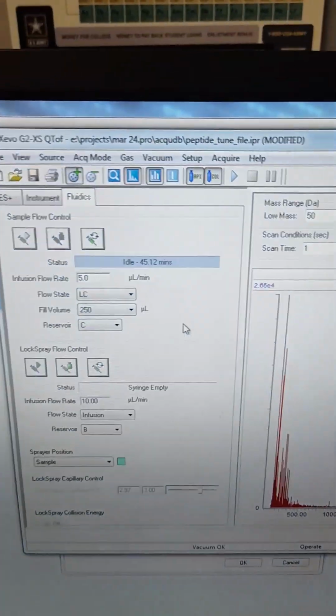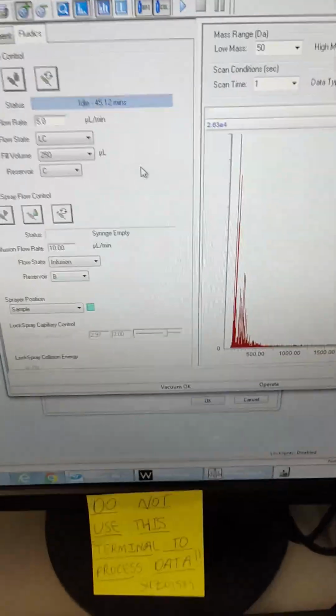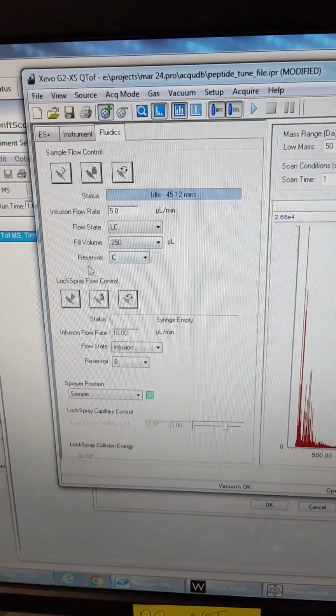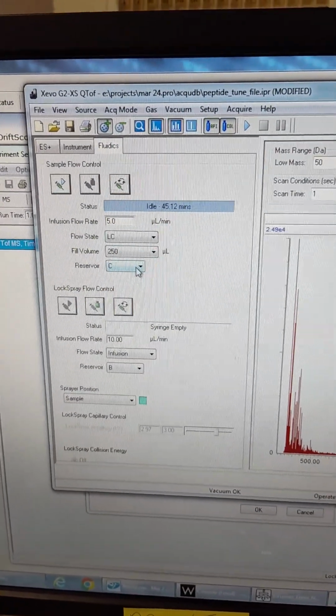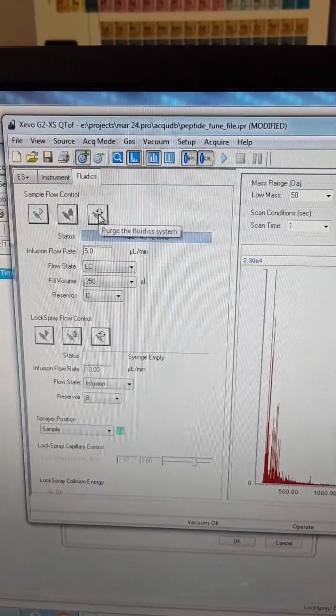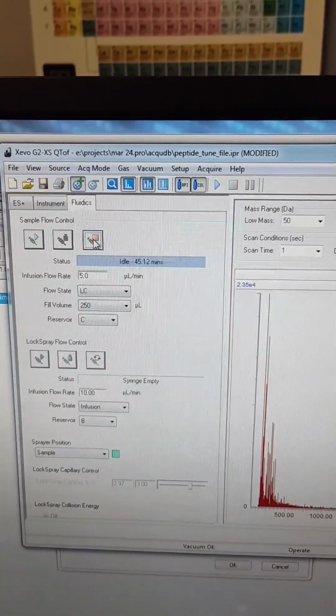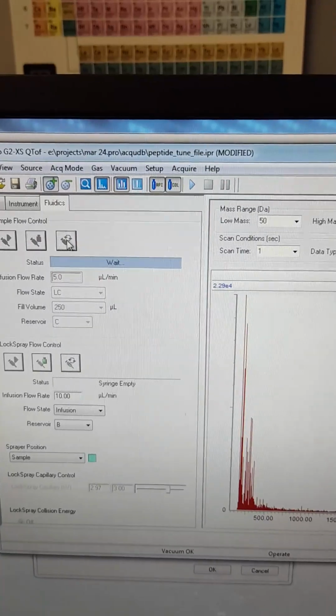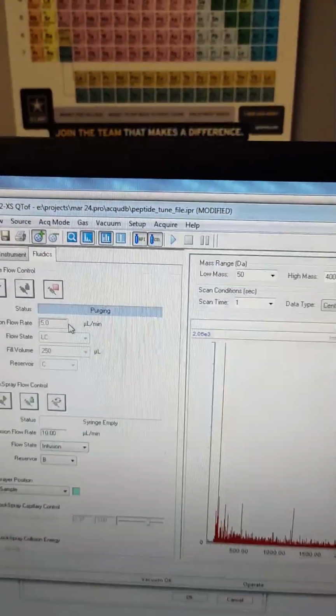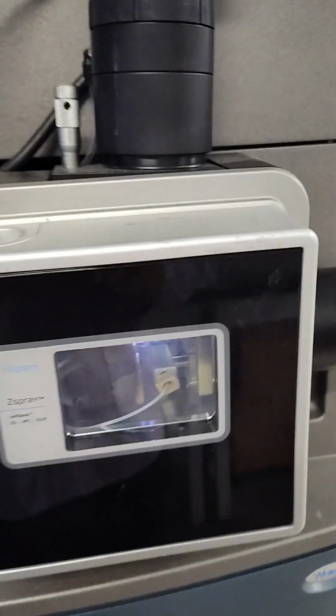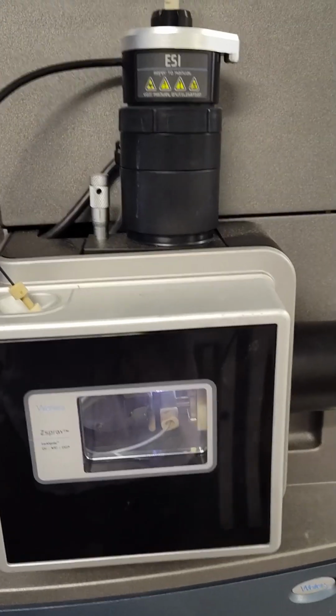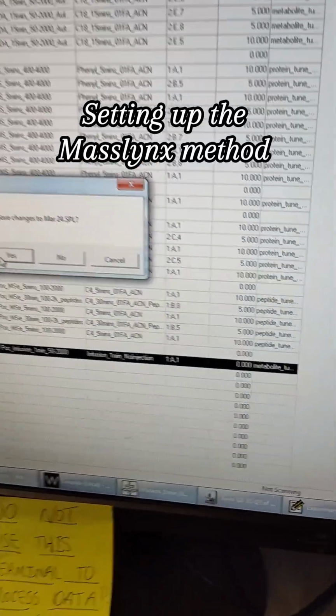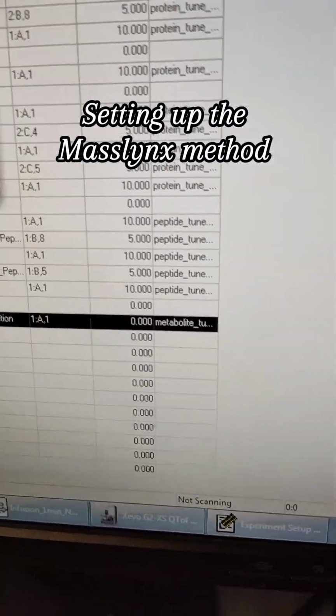And then we'll purge. We're going to go ahead and purge 3 times. Make sure that you are on reservoir C when you hit purge. And then you're just going to hit the purge the fluidic system here on C. We're trying to pump through the actual sample syringe. It's important to do the calibration through the same sample syringe that you're spraying your sample through so you get the best calibration.